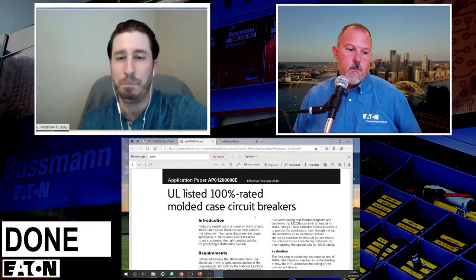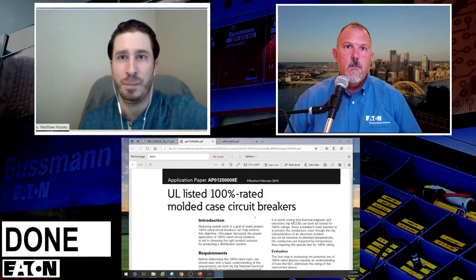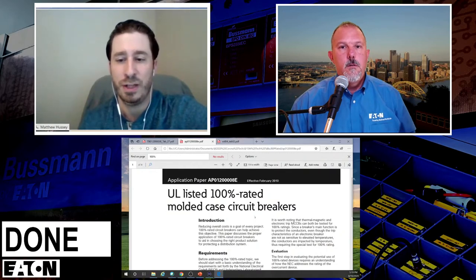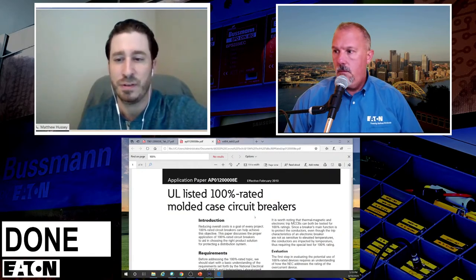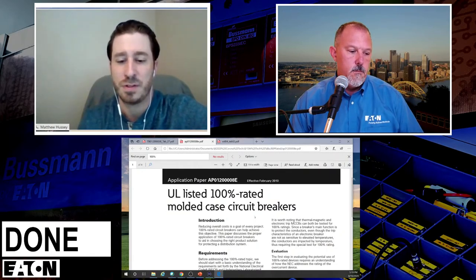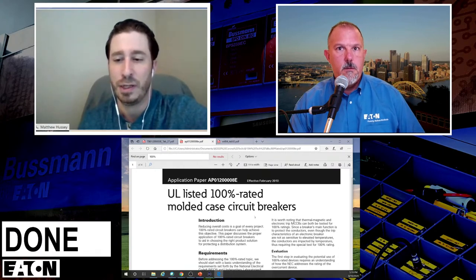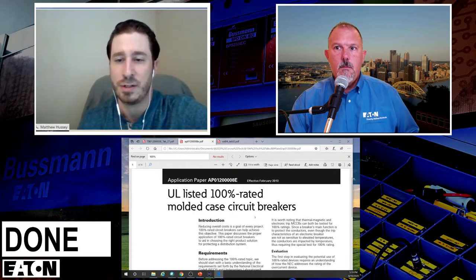And so you'll find that there are specialized designs, and that's usually what causes some of those restrictions that you see around NEMA classifications. Typically, if they're relying on passive cooling, you're going to miss out on an ability to have NEMA 12 designs or things like that. Usually subsequent limitations come into play with the choice of a 100% rated application.